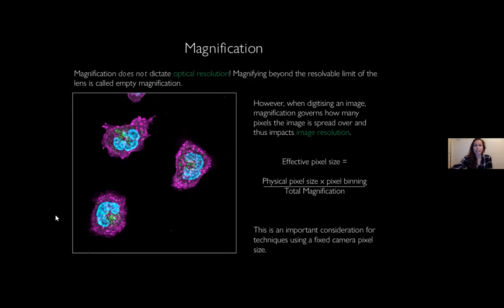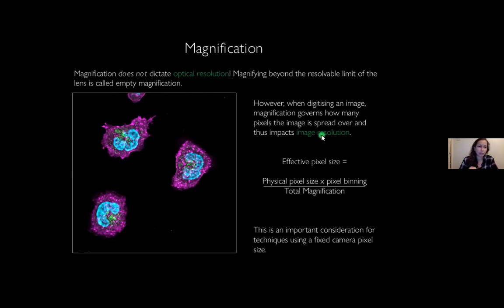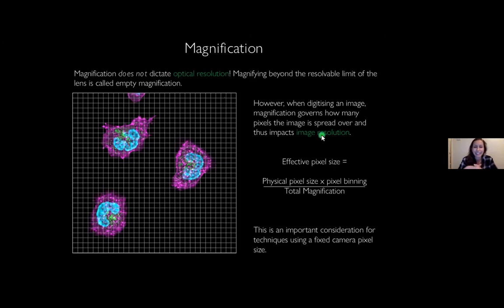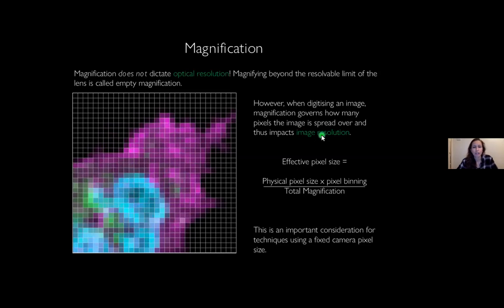Where confusion might arise is that although magnification does not govern optical resolution, it does impact the effective pixel size of a digitized image and therefore the image resolution. Image pixel size is simply the physical size of a camera pixel — accounting for any binning — divided by the total magnification. If we magnify a smaller region over the same number of pixels, we improve the image resolution, but this only improves up until the point where we meet the optical resolution. After this, there's nothing further to be gained by magnification. You can learn more by following the tea break talk on Nyquist sampling.